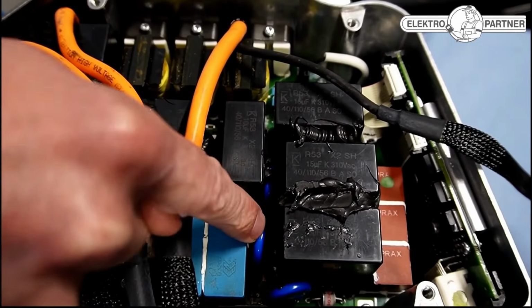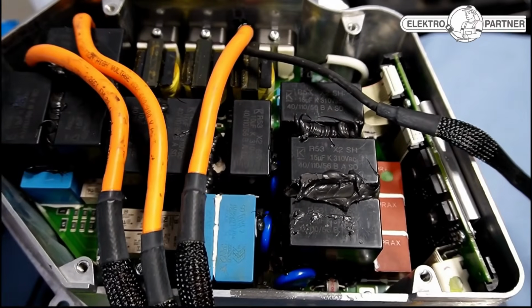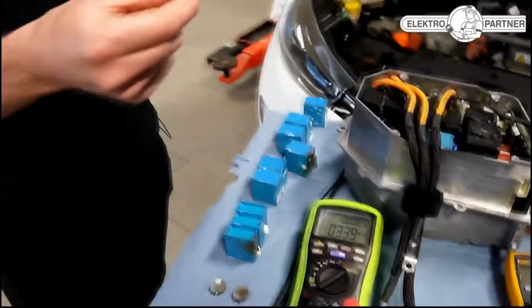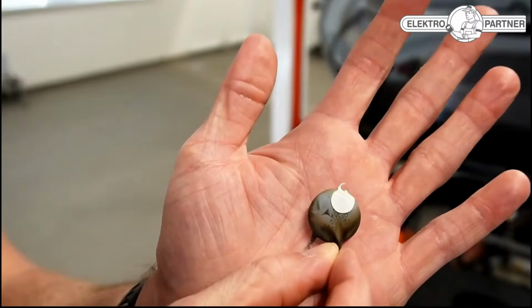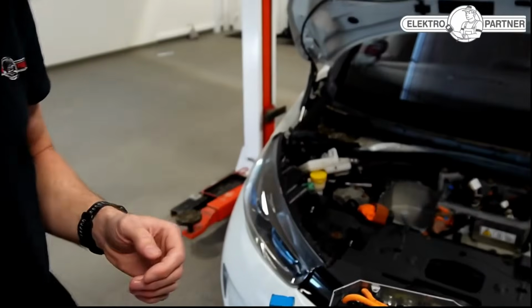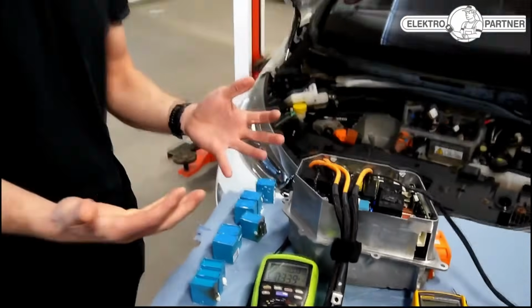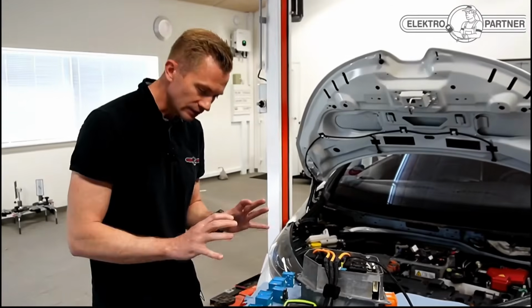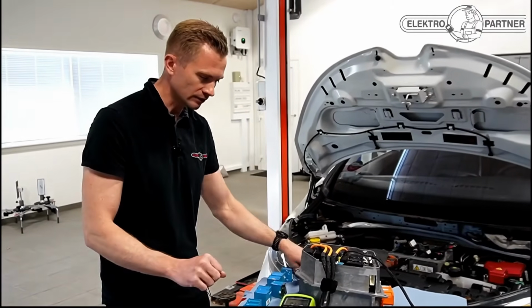Down here on the side, there are 3 varistors, and we've replaced those as well. You can try to take a look at one of the old ones here — it looks like this, so it's obviously been hot. Since it's an overvoltage protection component that's supposed to protect everything at 500 volts, we thought we should probably replace that as well during the same repair.